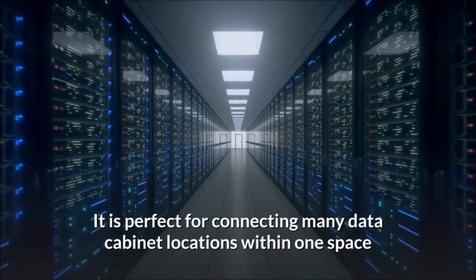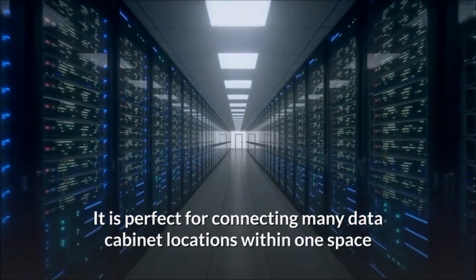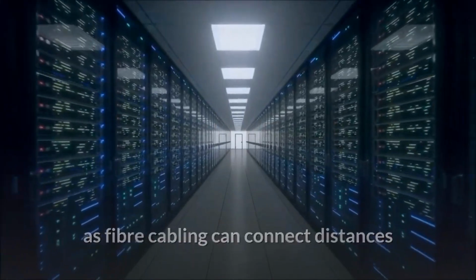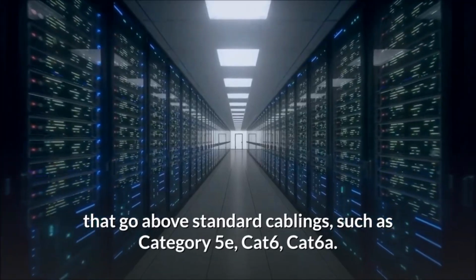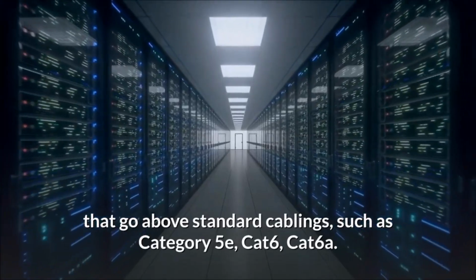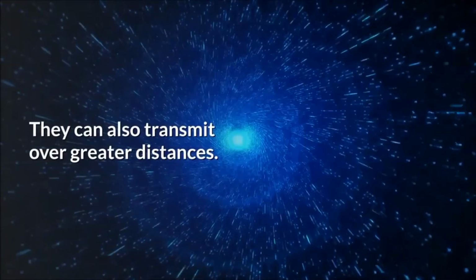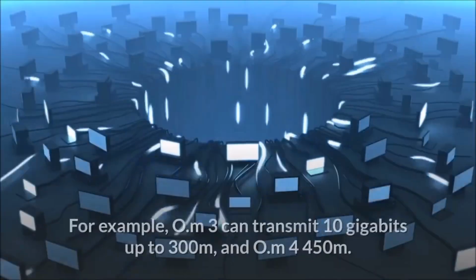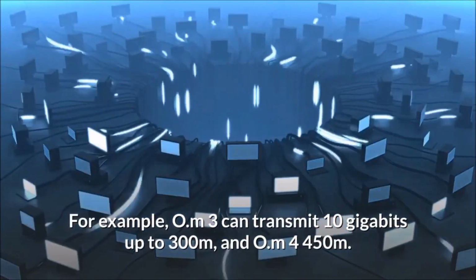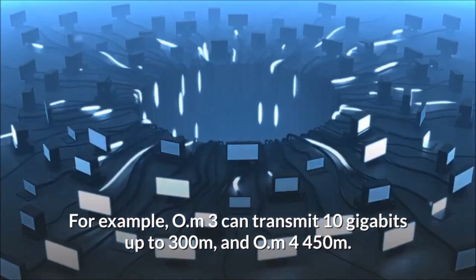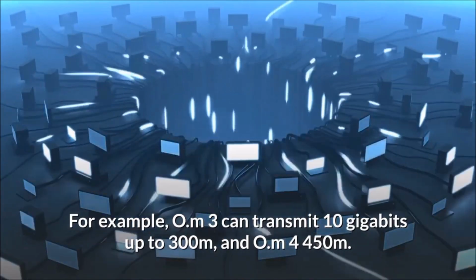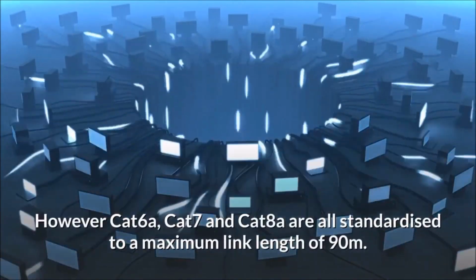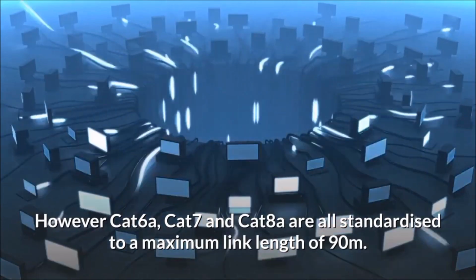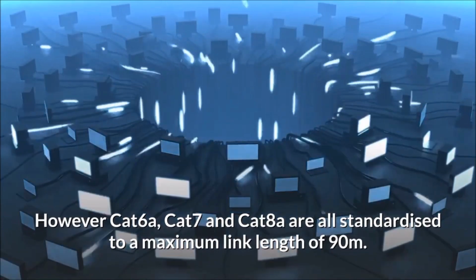It is perfect for connecting many data cabinet locations within one space, as fiber cabling can connect distances that go above standard cablings, such as Category 5E, Cat6, Cat6A. They can also transmit over greater distances. For example, OM3 can transmit 10 gigabits up to 300 meters, and OM4 450 meters. However, Cat6A, Cat7 and Cat8A are all standardized to a maximum link length of 90 meters.